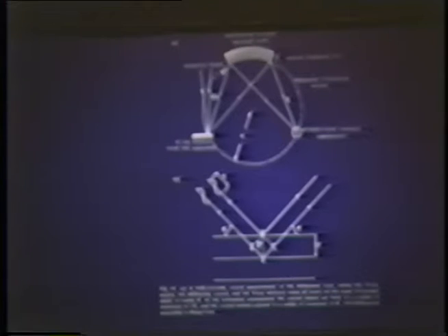But the major limitation is that only 1 or 2 elements can be analyzed at a time, because you would only have 1 or 2 crystals here. So this might be the crystal where you're only going to deflect, say, the sodium X-rays. So you'd have to count for a certain period of time to collect the sodium X-rays, but you might have another crystal here for detecting, say, the chlorine X-rays, which you could do in turn. The next slide, please.